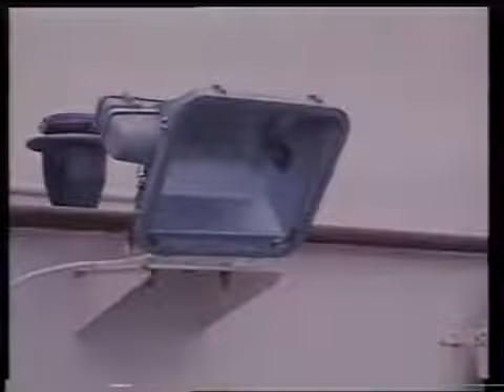No lamp should be changed while power is connected to them. This is especially true in the case of sodium lamps. They work with very high voltages. Also, when you're changing quartz iodine lamps, do not touch the quartz envelope of the lamp with your fingers, as this will shorten the lamp's life and lower its efficiency.